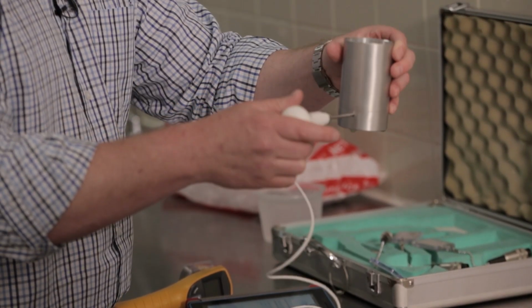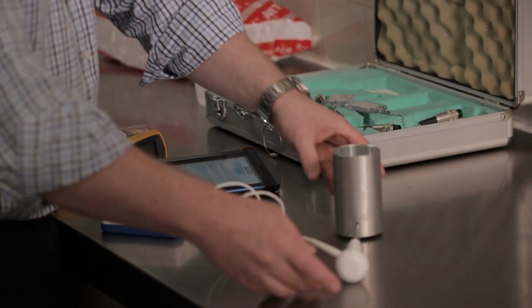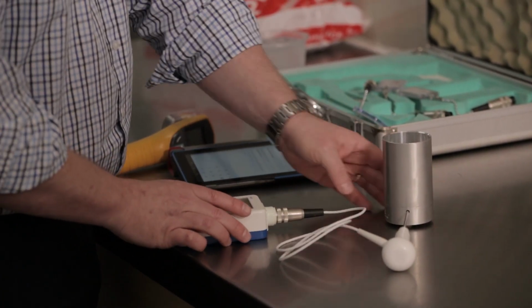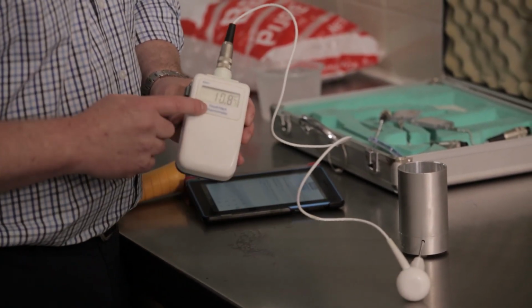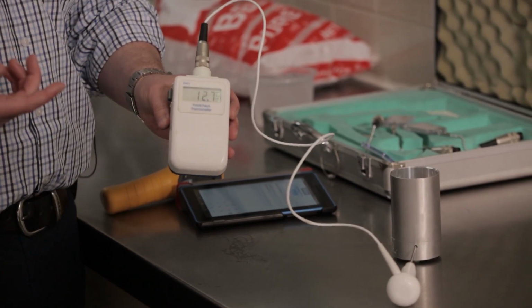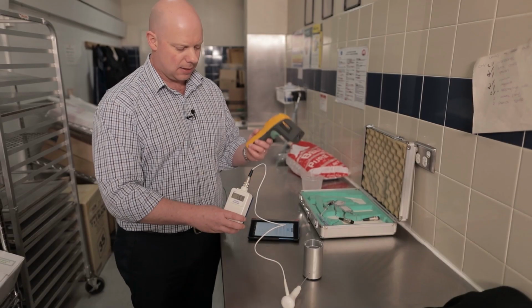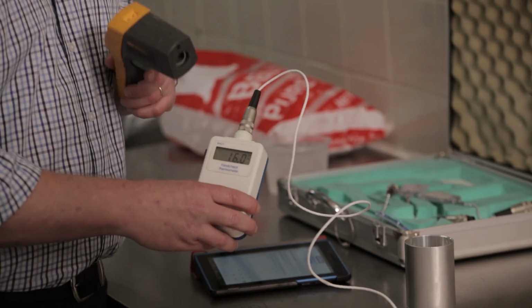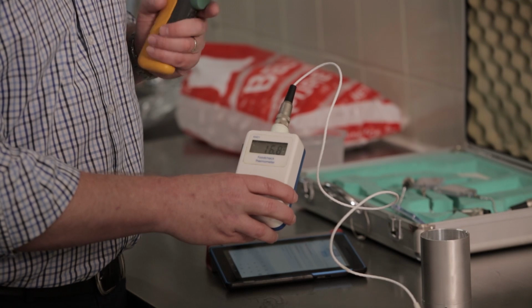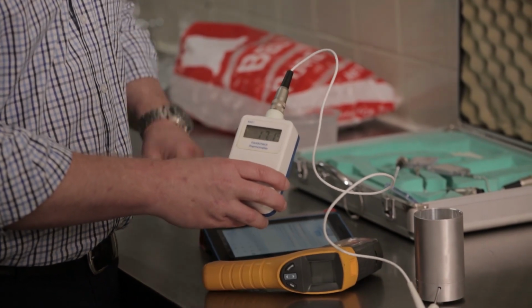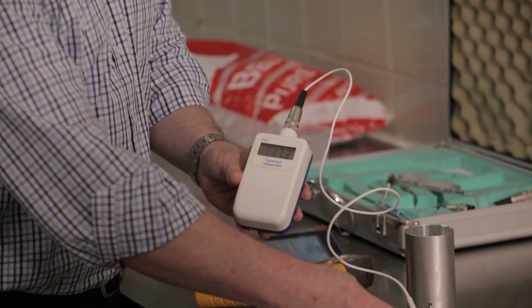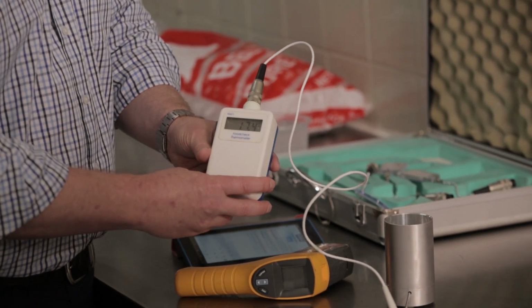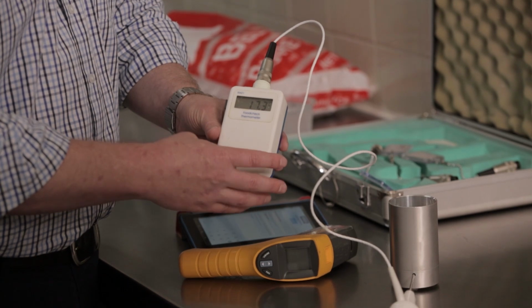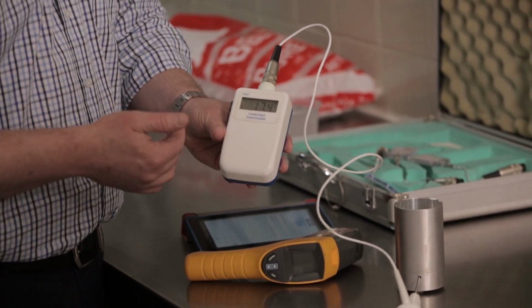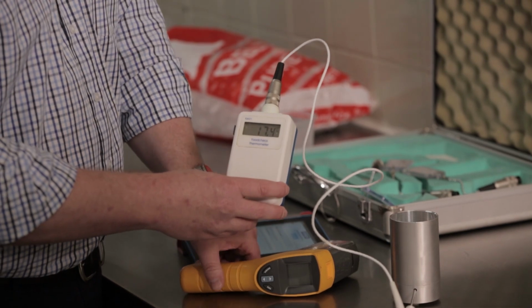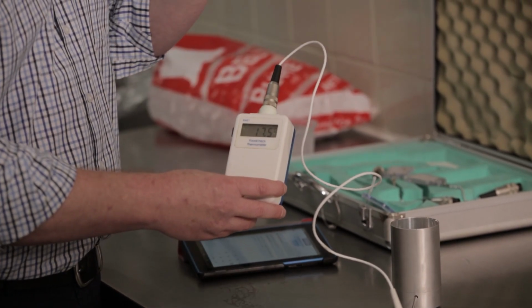We use one of these little holes in the bottom there, and we just let that sit. And what we're doing is we're just waiting for this digital reading just to regulate, stop moving, to make sure that when we do our infrared check, that this isn't still moving. All right, we want to make sure that we get the most accurate reading. So we just wait for that to regulate. Usually it takes between 1 or 2 minutes. And it's just come back down a little bit. So it's gone to 17.4, 17.3. So I'm fairly comfortable now that that has regulated to a point where I can use the gun.